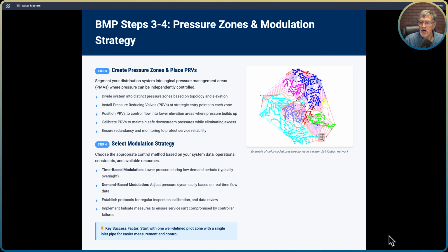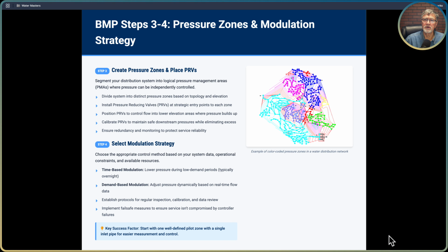Time-based modulation is one, and this is probably going to be your cheapest one because you're basically going to have a PRV with a timer on it, and it's going to adjust pressure at preset times during the day. That's going to lower your pressure overnight and raise it again during the day. You set that, and that's what's going to happen. Those are going to be your cheapest automated PRVs: time-based modulation.